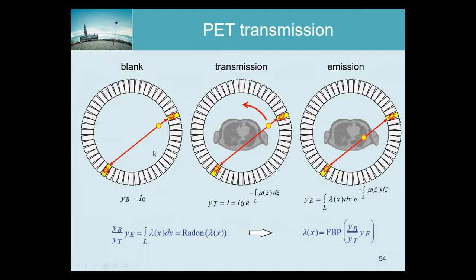The scanner could automatically take those sources out of the shielding and make them rotate in the field of view, close to the detector. While they were rotating, the scan would be acquired. Early in the morning, the scanner would wake up while no one was there and start doing a long blank scan of half an hour or an hour. During a blank scan, the source is rotating all the time, so every LOR gets to see the rod source, because the rod source trajectory will cross every LOR of the scanner.